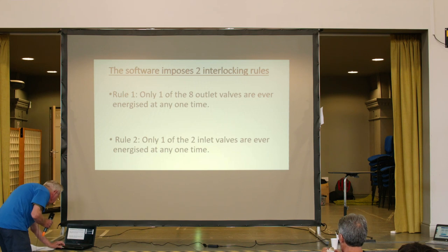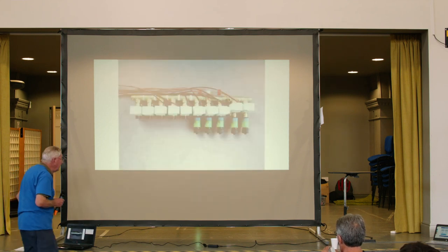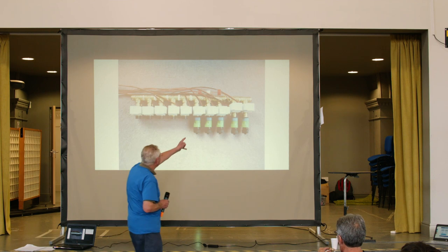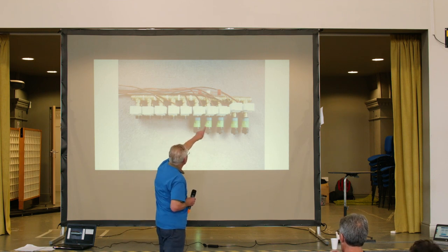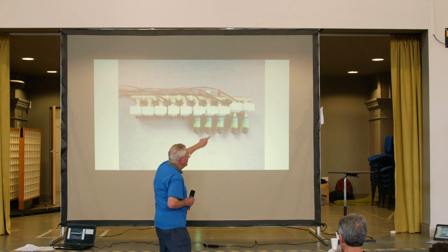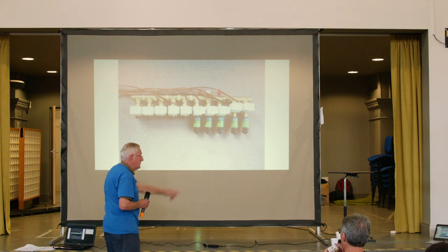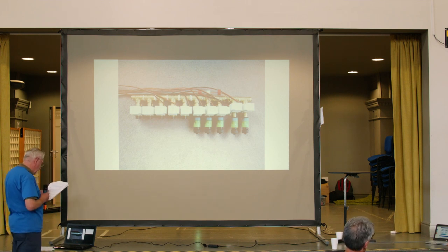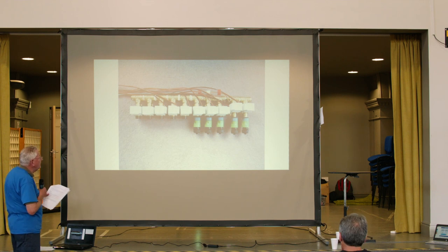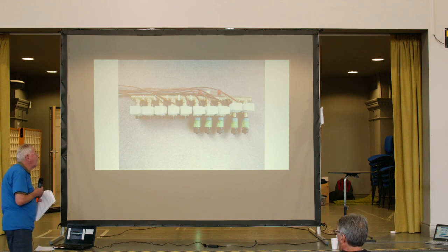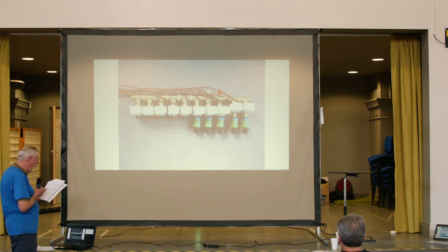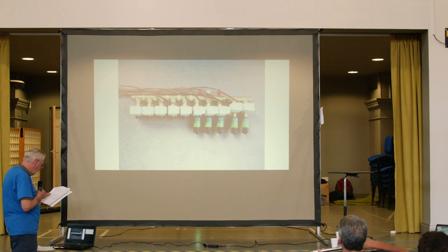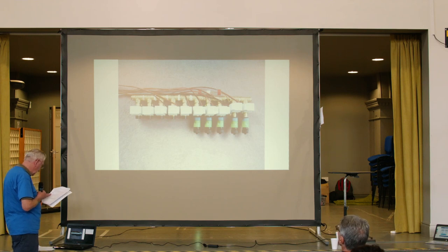There's also a flow sensor between those two inlet valves and the rest of them — you can't see it very well on here, but there's one to look at later. By positioning it where it is, the software always knows, when it's receiving a signal from the flow sensor, where the water's coming from and where it's going to, so it can be properly allocated to the correct outlet and source.